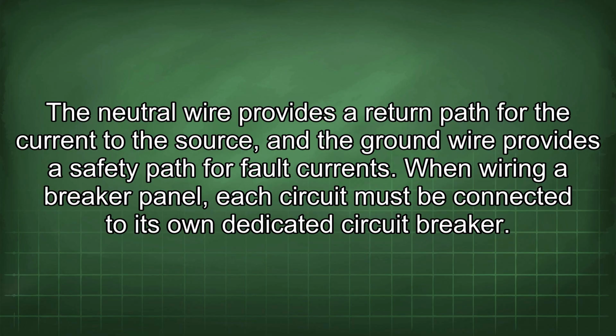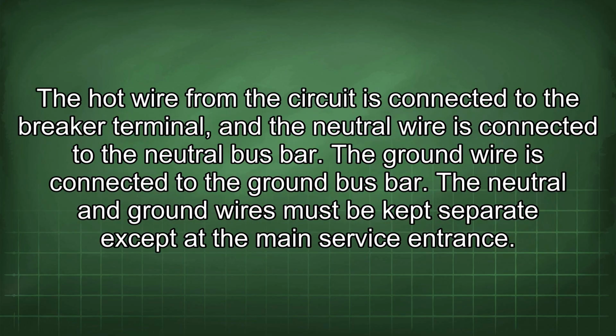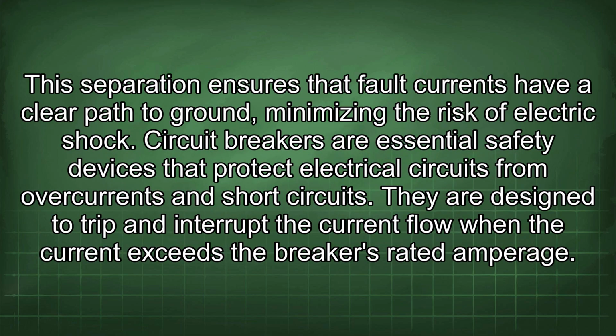The neutral wire provides a return path for the current to the source, and the ground wire provides a safety path for fault currents. When wiring a breaker panel, each circuit must be connected to its own dedicated circuit breaker. A hot wire from the circuit is connected to the breaker terminal, and the neutral wire is connected to the neutral bus bar. The ground wire is connected to the ground bus bar. The neutral and ground wires must be kept separate except at the main service entrance. This separation ensures that fault currents have a clear path to ground, minimizing the risk of electric shock.